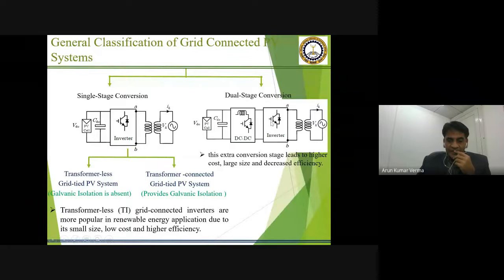And in dual stage, basically you have PV panels, a DC stage which I've already told you about, and then an inverter having isolation, and then the grid. So this DC converter serves two purposes: MPPT, maximum power point tracking, and injecting active power into the DC link.